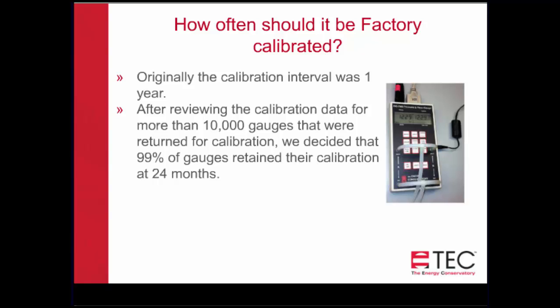when was the time that it was last calibrated and how much time is it now. So from that, we were able to determine that interval. And we decided that since 99% of all of the gauges retained their calibration at 24 months, that we changed our calibration interval to 2 years. So a factory calibration is 2 years.